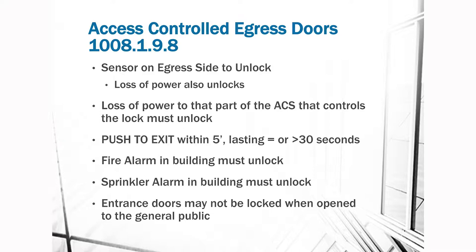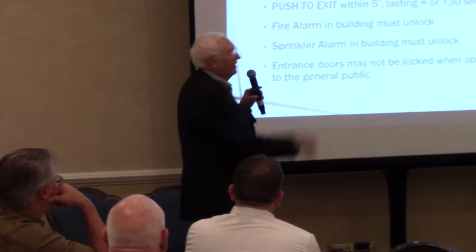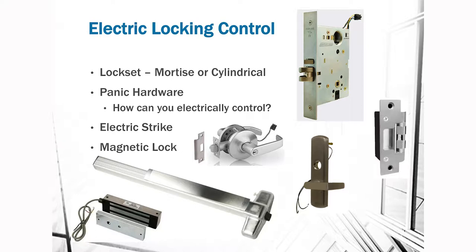By the time you've done all that you've got kind of a mess. What if you have a hurricane, you're out of power for four days, no generator, no batteries? The way in is probably unlocked too, because we don't have many locks that lock the way out differently from the way in. I found one in England — a really great lock with two solenoids: fail-safe on the inside handle and fail-secure on the outside handle.